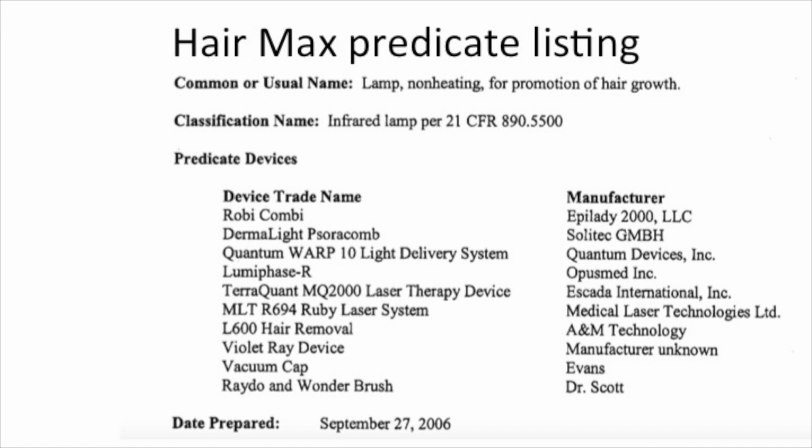By today's standards for 510K submissions, you couldn't do something as wild as this and really get anywhere. You would need to specifically list each parameter of your device and compare it to the predicates. And you would need to pick preferably one or at the most, say, two other devices.